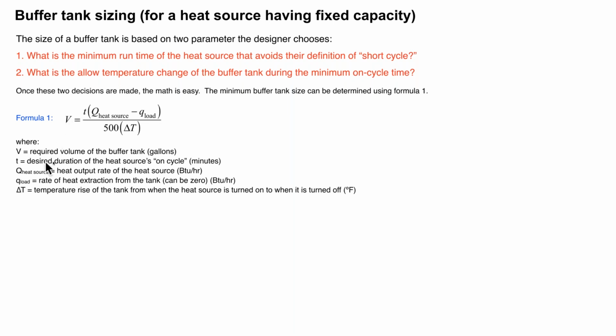Well, T here would be the desired duration of the heat source on cycle. Let's say we're going to make that 10 minutes, okay? We have to know the heat output rate in BTUs per hour of our heat source. And I should mention again, this formula is independent of what the fuel is or what the heat source is. It's just a rate of heat production from some heat source.